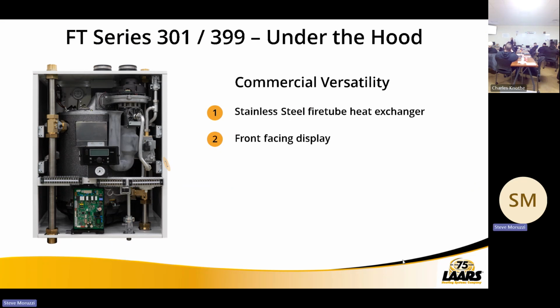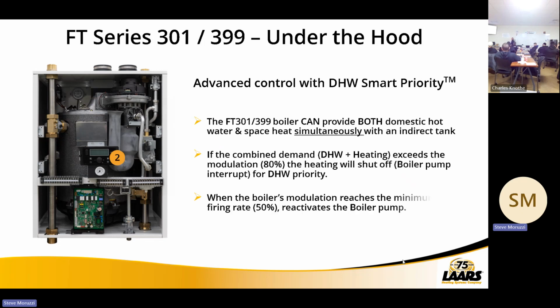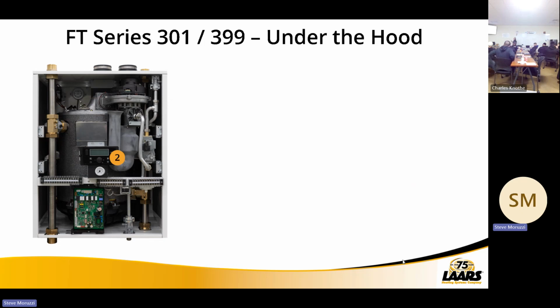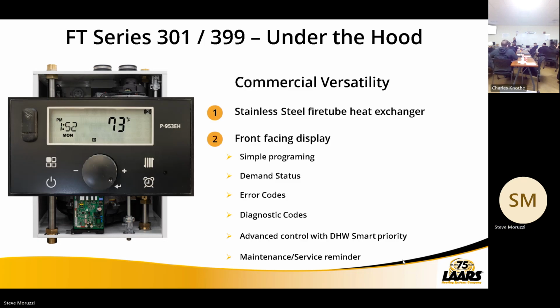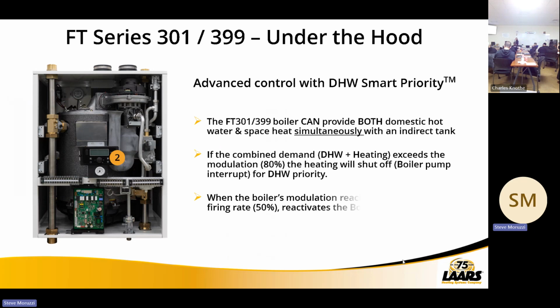Facing display, again, you guys should be familiar with that. We already talked about that. This internet is running slow again. So again, simple programming, demand status, error code, diagnostic code. We do have the advanced technology for smart priority. If you don't want smart priority, you can throw the dip switch off and go to traditional priority. Okay. We'll talk about that as well. And you also have the maintenance and service reminders on the display, so the end user can see that and call in for service. So I've talked about this before.